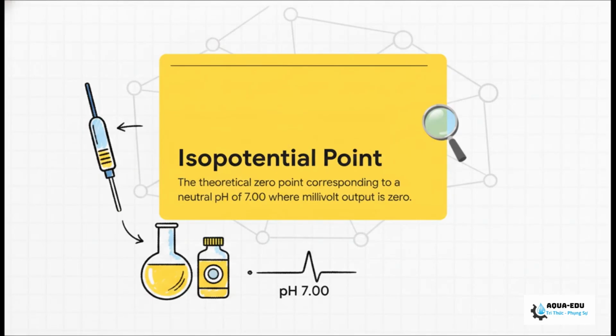Understanding the isopotential point is the real secret to mastering this system. Think of it as the theoretical 0 point of a pH electrode. It corresponds exactly to a neutral pH of 7.00, which is where the millivolt output is essentially 0.